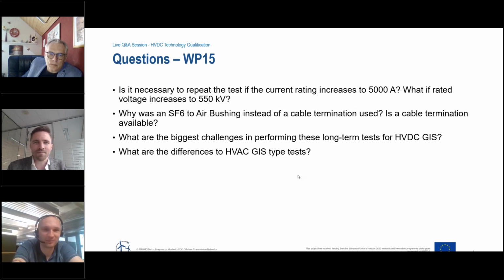The major difference is that with the dielectric tests, we have added superimposed impulse voltages. That means you do not just test first the AC withstand and then switching impulse or lightning impulse withstand, like it's done in AC, but you have the DC and at the same time the lightning impulse and the switching impulse superimposed. This makes the test more effort. I think Hong can confirm that because you need two generators at the same time, and a divider that can also measure at the same time.